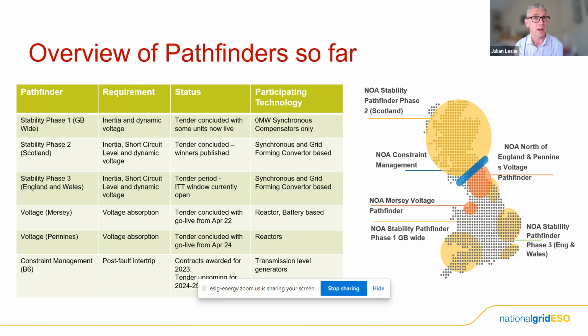So we expected existing assets would come to the market, which have tweaked how they operate to provide inertia and voltage control. We weren't paying existing generators that were going to be on anyway and providing these services for free. This is where generators had to behave differently, operate differently, or invest in their kit in order to provide these services. So in phase one, for example, we got an old CCGT that was about to be demolished and decommissioned, actually repurposing itself and providing the inertia without the gas turbine. So it runs synchronously with the system. We get the rotating mass and the voltage control from that. And it's provided jobs and security.